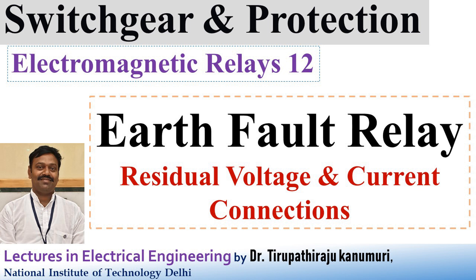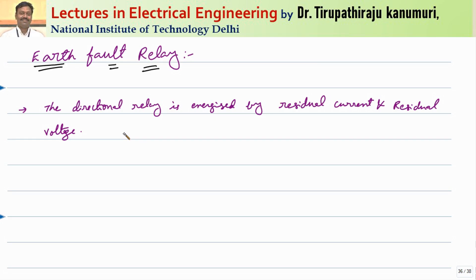Hi all, today we are going to discuss about earth fault relay connections for three-phase circuits. In order to get the earth fault relay using a single relay, it needs three separate CTs and three separate PTs. The directional relay is energized — we go for a single directional relay which is energized by a residual current and residual voltage.